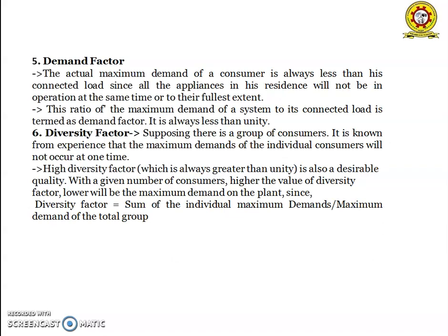And next one is the demand factor. The maximum demand of a consumer is always less than the connected load, since all the appliances in the residence will not be operated at the same time. It is the ratio of the maximum demand of the system to the connected load. Its value is always less than 1.